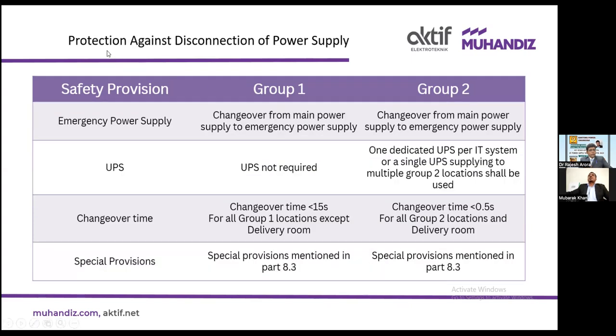Okay. Second is protection against disconnection of power supply. So the first part is the use of emergency power supply. It must be there for Group 1 as well as Group 2 locations. It can be a very large UPS or a diesel generator set. Okay. The second part of the safety provisions is UPS. For Group 1 locations, UPS is not required. You can rely on the generator. But in Group 2 locations, one dedicated UPS per IT system, or a single UPS supplying multiple Group 2 locations, shall be used. Okay. So a UPS backup along with the generator backup must be used in Group 2 locations.